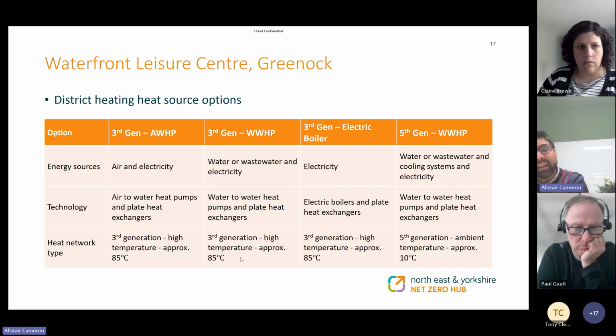Now, because we're not taking a fabric-first approach, the vast majority of the buildings that have been mentioned on this presentation slide are operating at high flow and return temperatures. So generally speaking, the waterfront leisure centre, the GMB, the police station, the ocean terminal, they're all operating at heating circuits in and around 80 degrees flow. So there wasn't an option immediately to reduce that flow rate without making significant changes to the building's heating systems by upgrading pipes, pumps and radiators and heat emitters, which wasn't something we wanted to do because that would further increase the capital cost of the investment.